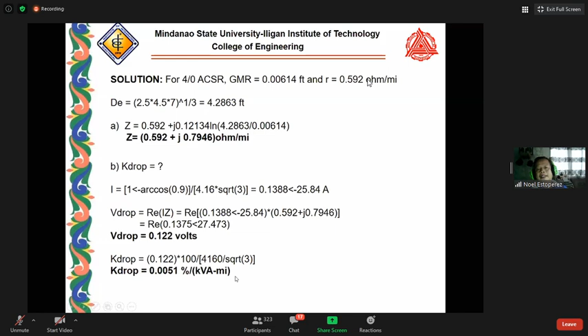So let us look at the segment from bus or node 0 to node 1, the segment with a length of 0.15 mile. Our K drop factor will simply be multiplied by 0.15 times 1675 kVA. The 1675 kVA from 0 to 1 is the sum of the loads downstream. So if we sum up these loads, this will be 1,675 kVA flow. So the voltage drop at node 1 will be 1.281.